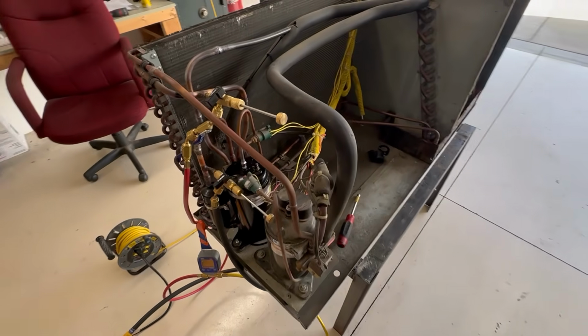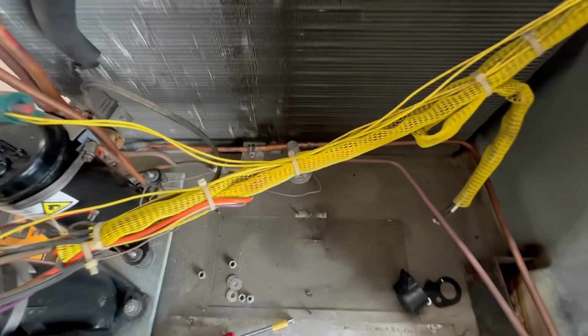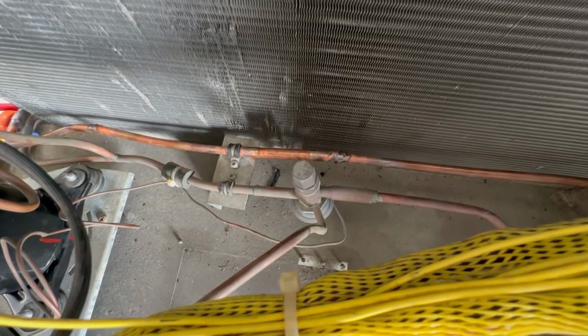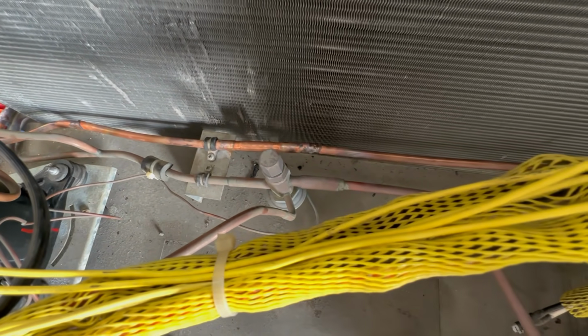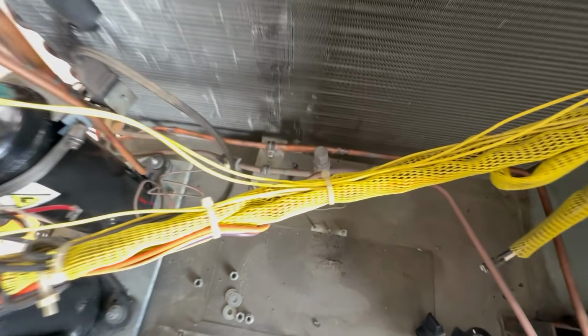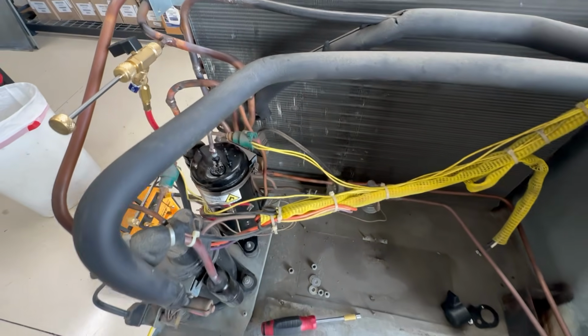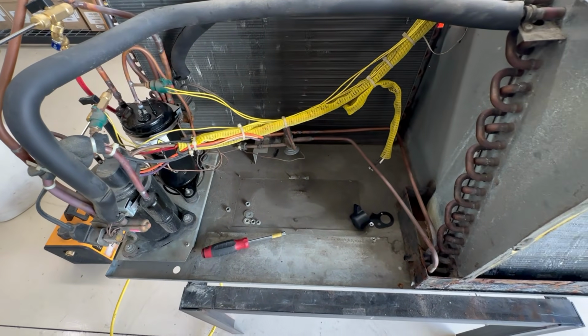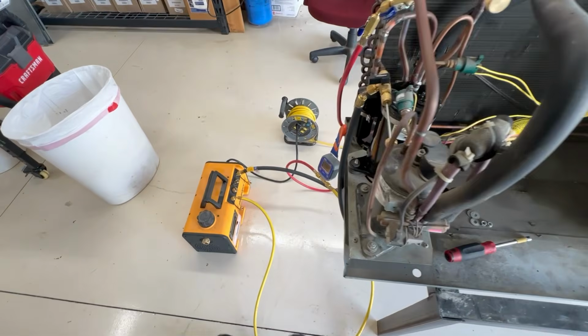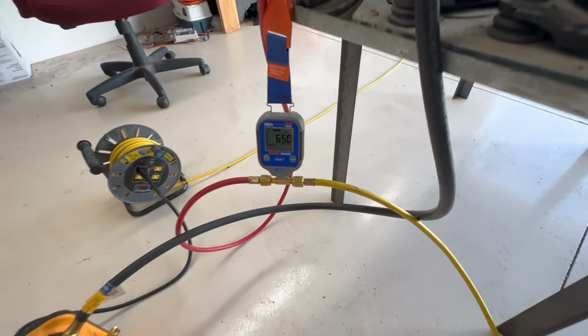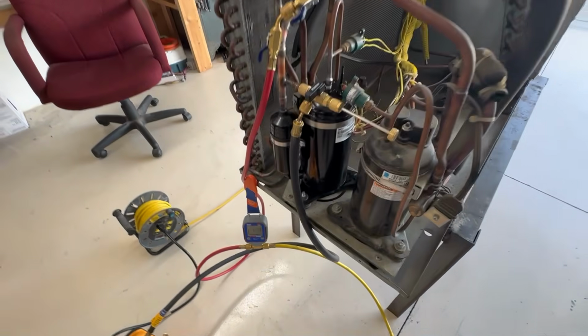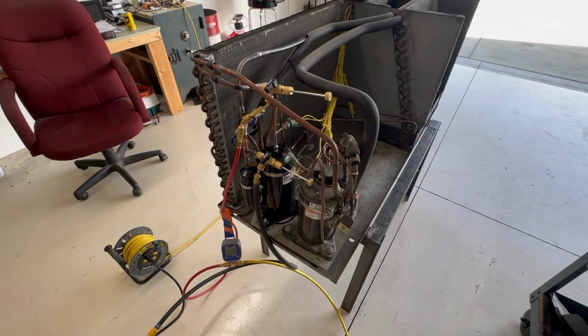So got it all back together. You can see, went from thermal expansion valve to a Bi-flo valve. Got everything back together, pressure tested everything, just trying to get the vacuum down on this thing. We're down to 650, so we're getting close. But yeah, close to charge with this one.